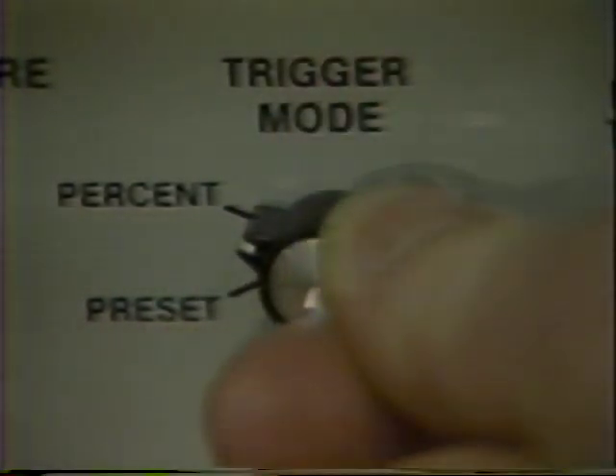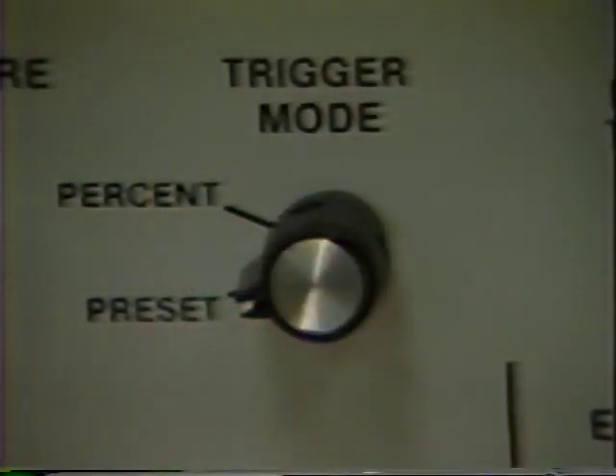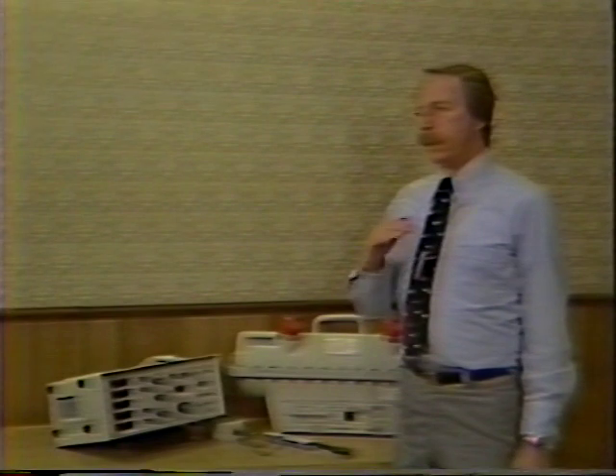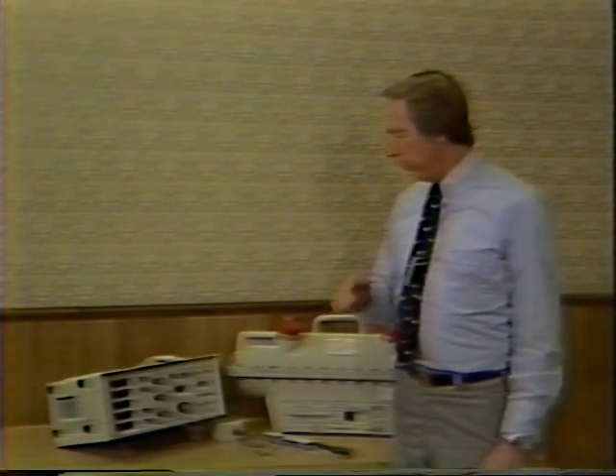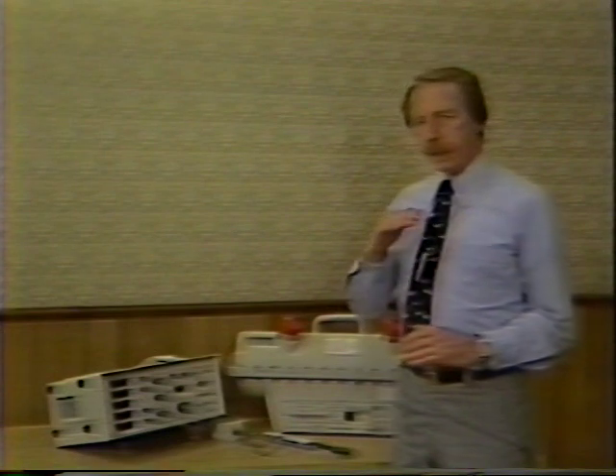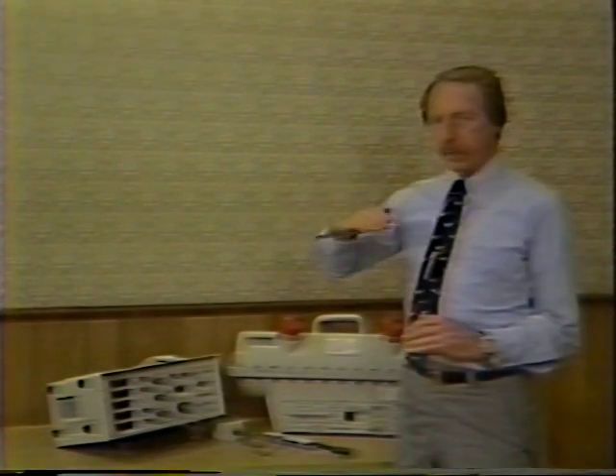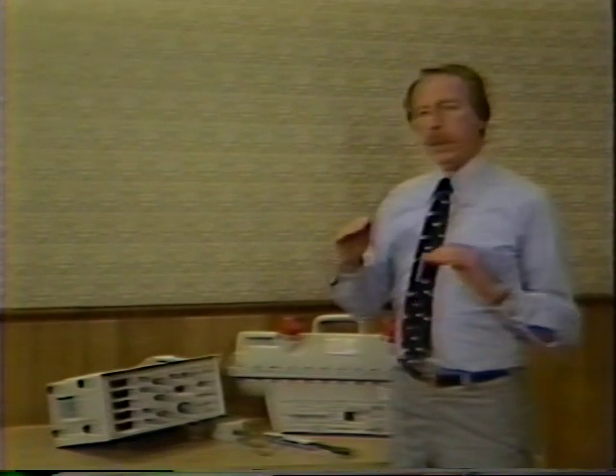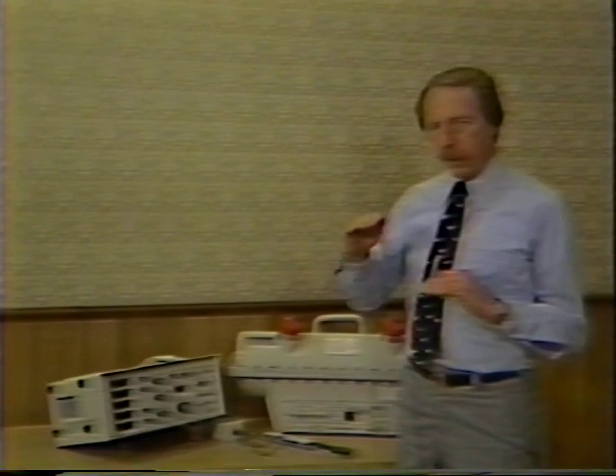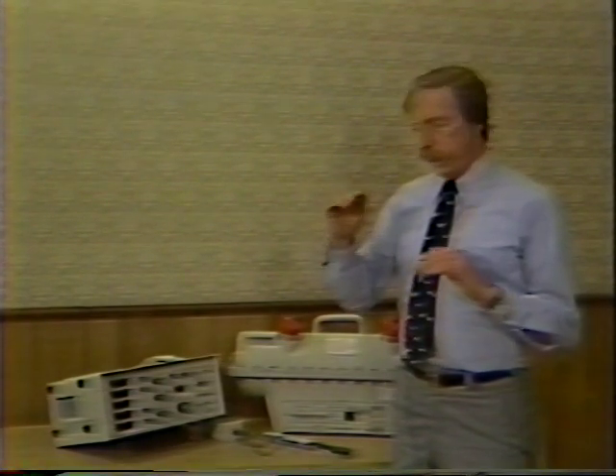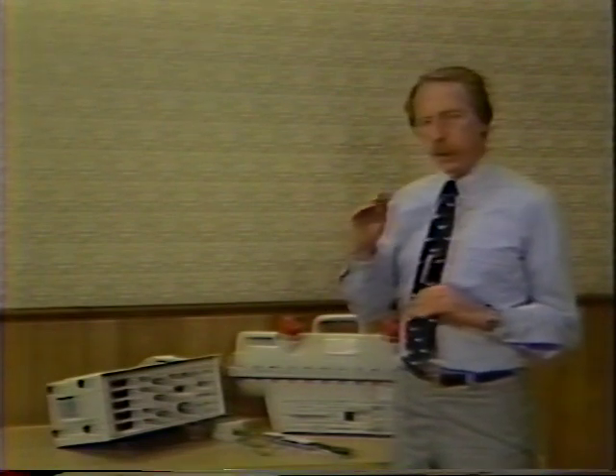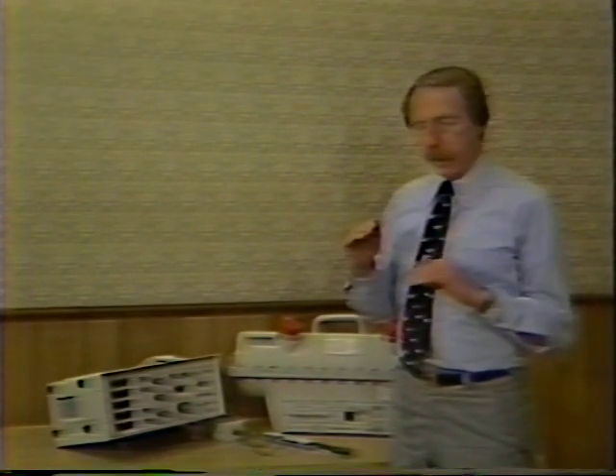It has two positions: percent, which is sometimes called automatic, or preset, which is sometimes called manual. In a percent mode, recall we had an American General Electric X-ray equipment. We are going to measure time at the 75% level. This position of the switch allows us to retain the 75% level as we move the kV setting on the generator up. Remember, we had 100 kV, and 75% of that was the 75 kV level. If we adjust the generator voltage up to 120 kV, this will automatically calculate 75% of the new value and set the threshold at the 90 kV level.